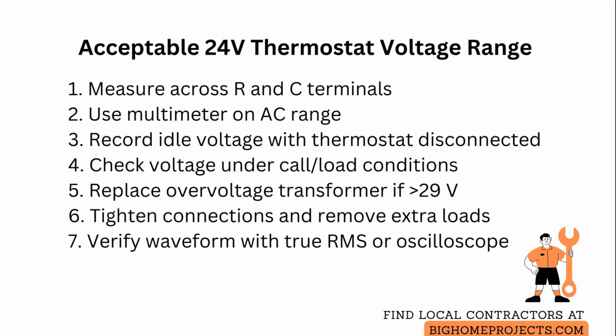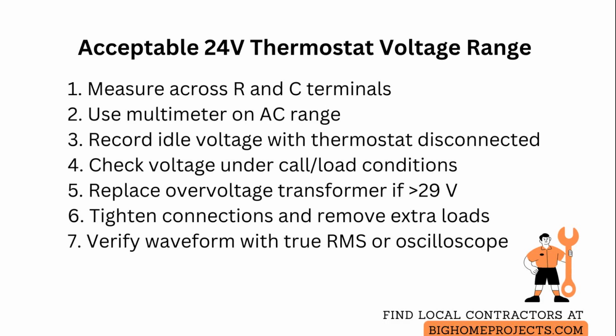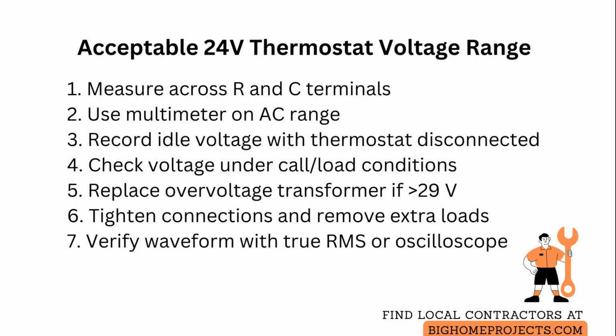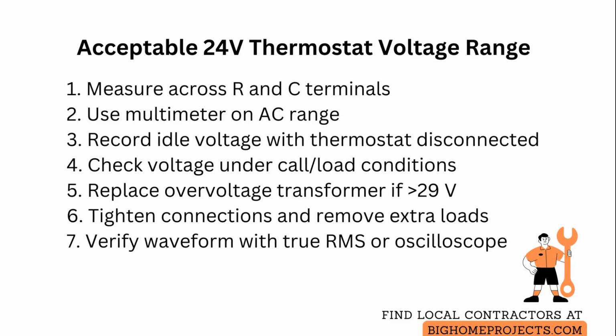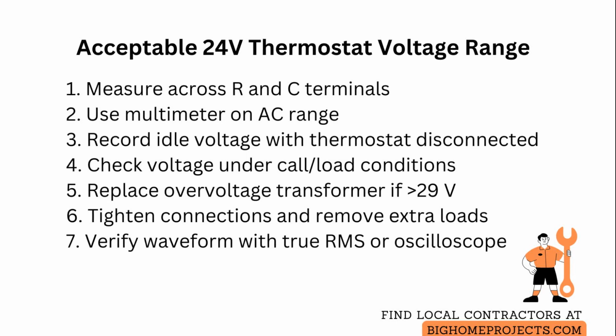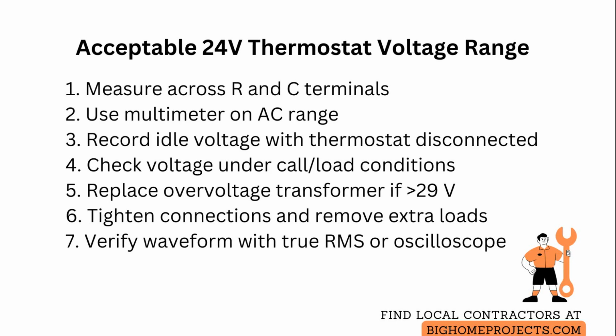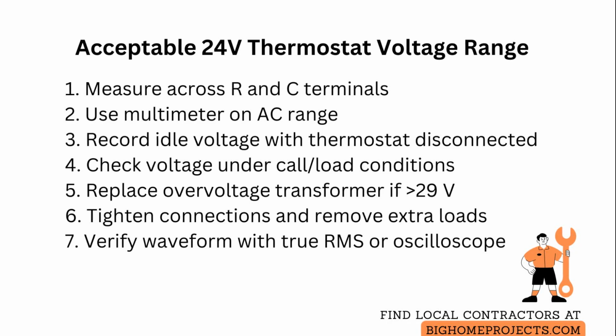When testing, also check for alternating current waveform distortion or significant voltage ripple using an oscilloscope or a true root mean square meter if available, because some inexpensive meters can mask poor waveform quality that still causes erratic thermostat behavior. Finally, always isolate power at the breaker before making wiring changes and verify transformer primary wiring to the correct line voltage to avoid safety risks.